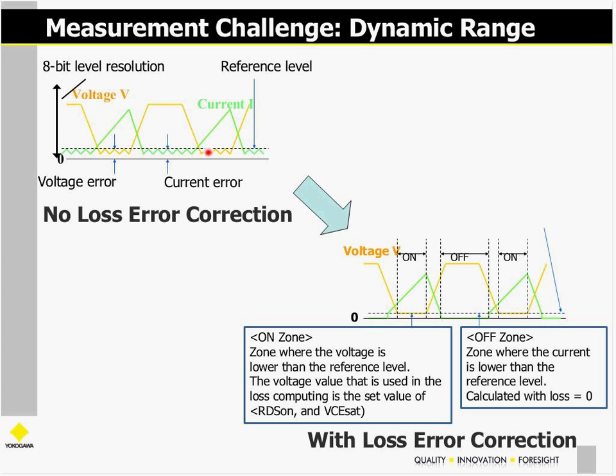I may not mind. I may just be making some rough measurements, and that may be fine. But if I really want to refine my measurements, I'll draw a threshold line that says below this voltage or current range, I want the scope to assume a given value. The scope permits you to assign that value. So the measurement challenge here is dynamic range, and the solution is to intervene with a feature that lets you tell the scope what values to use in its calculations below these reference values. So again, you have a voltage error and a current error as well.